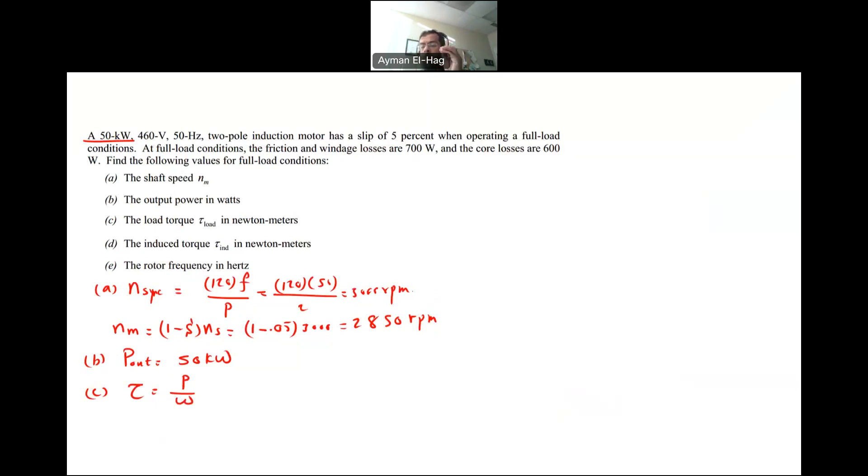We have to know which torque we are looking for to specify which power we should use. So here we want to find the load torque. Load torque, it means that the torque that is connected to the load, or basically it's related to the output power. So here your torque at the load is equal to the P out divided by the rotational speed of the rotor, which is omega M. So your torque at the load equal to P out, we already know it, which is the 50 kilowatt, 50 times 10 to the power 3 divided by omega M is basically NM, which is 2850, and multiply it with the conversion factor 2 pi over 60, and this will give me a total torque equal to 167.5 Newton meter.